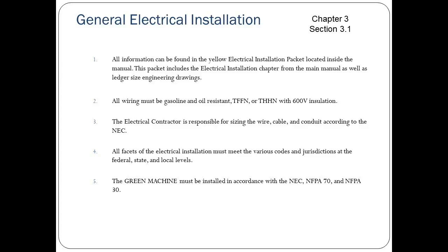All wiring must be gasoline and oil resistant, TFFN, or THHN with 600 volts insulation. The electrical contractor is responsible for sizing the wire, cable, and conduit according to the NEC. All facets of the electrical installation must meet the various codes and jurisdictions at the federal, state, and local levels. The Green Machine must be installed in accordance with the NEC, NFPA 70, and NFPA 30.